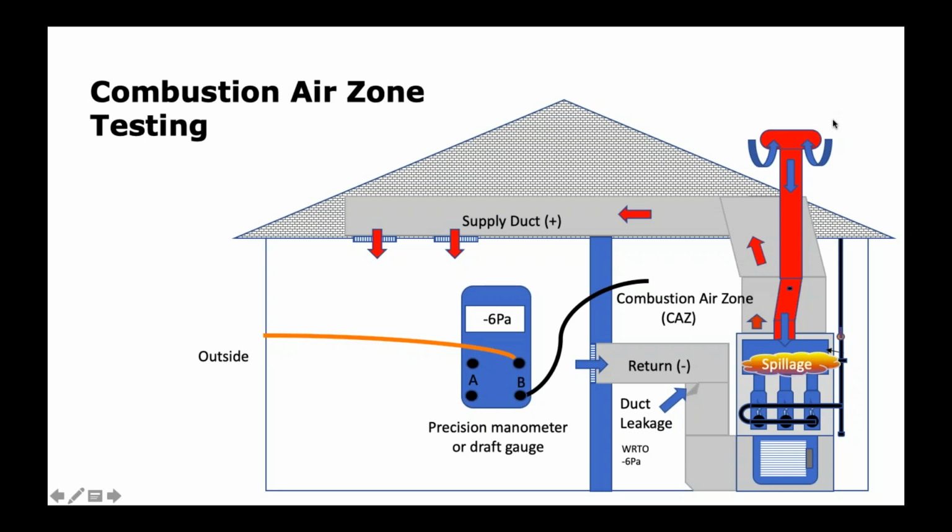And that's enough pressure that it's sucking the flue gases backwards down the stack and causing spillage. Then that spillage is going to leak right over here into that duct leak, and we're going to circulate that spillage throughout the house. If we're making carbon monoxide, this could be a serious problem for that burner. We're robbing that burner because we're putting flue gases in the room, replacing clean air with oxygen deprived air. Now we have a recipe for making carbon monoxide, because we're spilling gases in the room that have less oxygen in them than they would get from outside. So, very, very important.